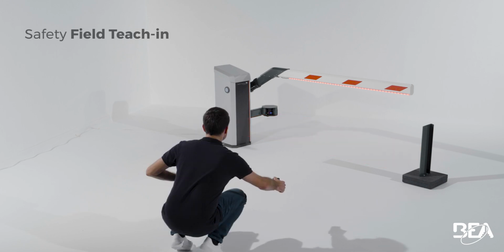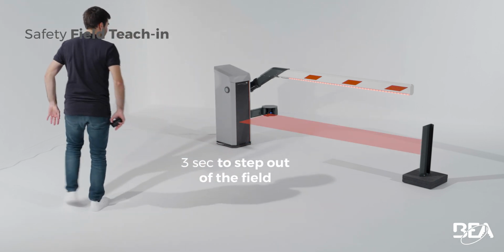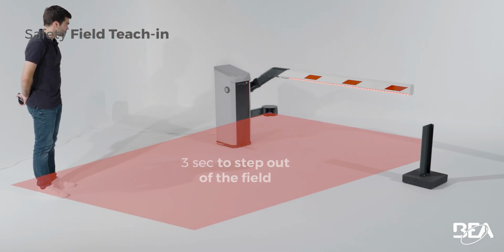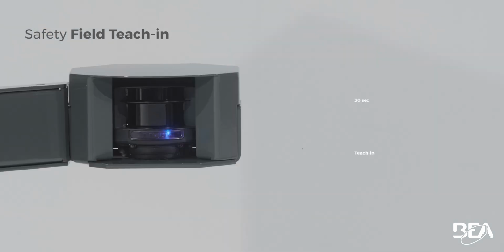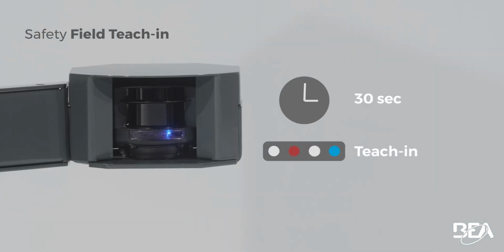After checking or adjusting the field dimensions, launch a teach-in. You have 3 seconds to step out of the detection field and clear it of any objects. Once the LED flashes slowly, wait plus or minus 30 seconds while the sensor learns its environment.